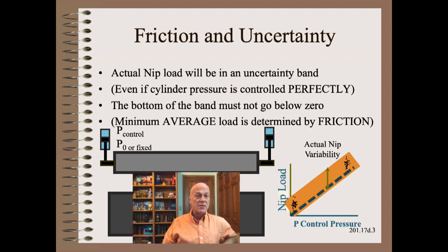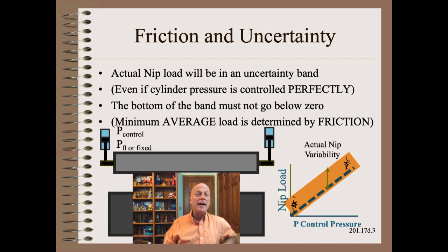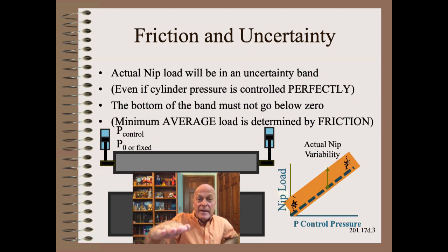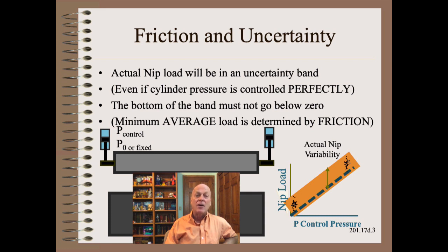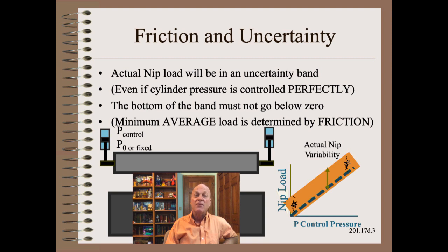The results will be that actual nip loads — not the ones you see on the control panel — will lie in an uncertainty band instead of on a line or at a set point. This is true even if the cylinder pressure is controlled perfectly. We can see here how we must adjust the calibration of zero such that bouncing nips never go to or below zero. That also means that low average nip loads are not possible with systems bound up with friction.